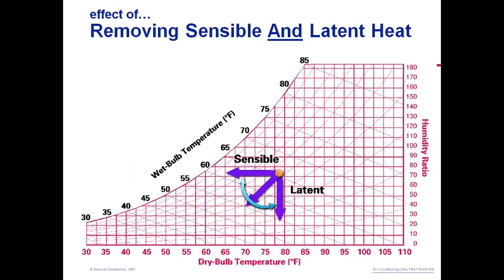There are eight psychrometric processes; six are indicated on the graph. If the initial point moves horizontally rightward, that is a heating process; leftward is cooling. Vertically upward is humidification — adding moisture without changing dry bulb temperature. Vertically downward is dehumidification — reducing moisture content. In inclined directions, it is a combination of these basic processes.